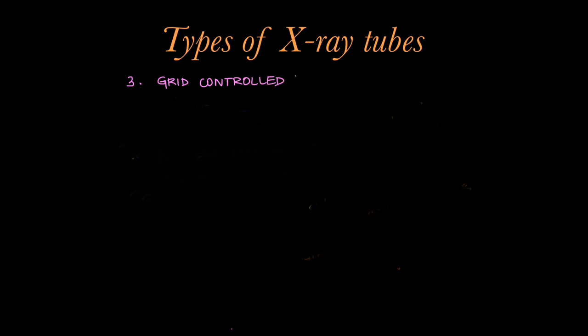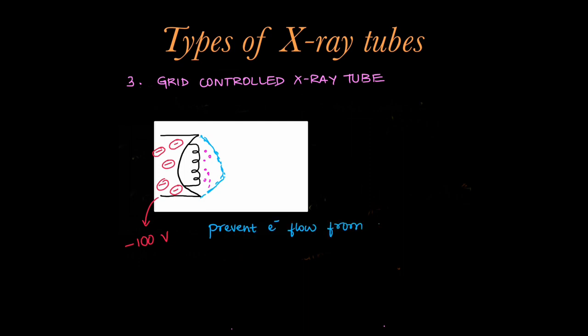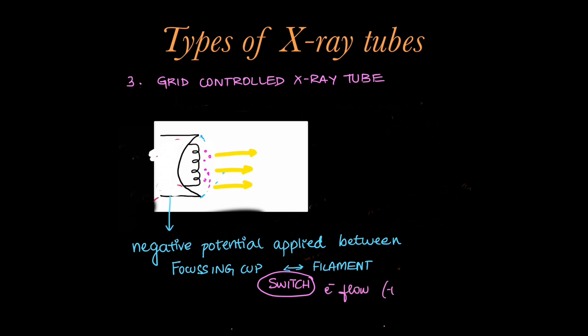Coming to the grid controlled x-ray tube, which is a short answer question for MD and DNB students. In this, the focusing cup is kept at a negative potential in relation to the filament at the cathode. Increasing the negative potential to up to minus 100 volts will stop the flow of electrons from cathode to anode and shuts down the tube current, acting as a grid to control x-ray production. That negative potential between the focusing cup and the filament, when increased or decreased, acts as a switch for tube current and hence controls x-ray production. These are used in DSA and cine-radiography x-ray tubes.